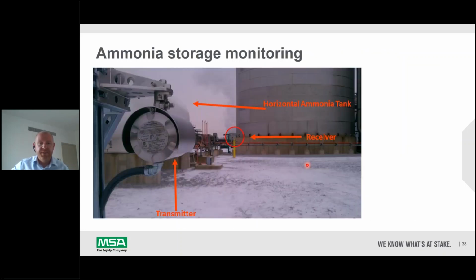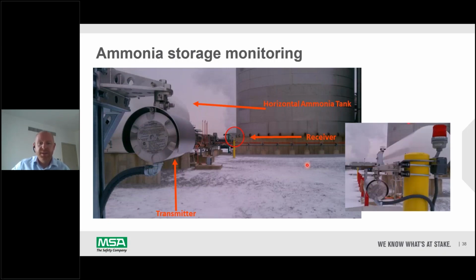So this is an image of ammonia storage monitoring. I can't remember which country this is in, but you can see here what they're trying to protect is a leak from this horizontal ammonia storage tank. So we have the transmitter, the source, and then we have the receiver about 20 to 30 meters away. So that is protecting from an ammonia leak in this area. And of course, this type of system can be used for a majority of combustible and toxic gases. So it's not just for ammonia. We use this in the oil and gas industry as well for boundary protection of sites.